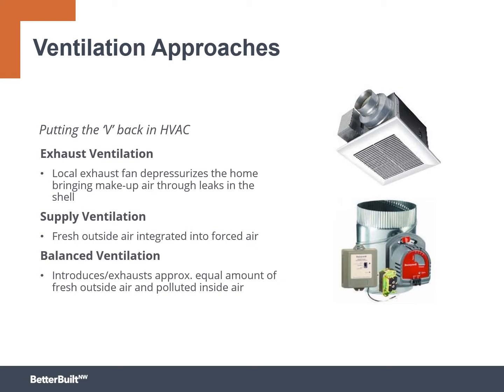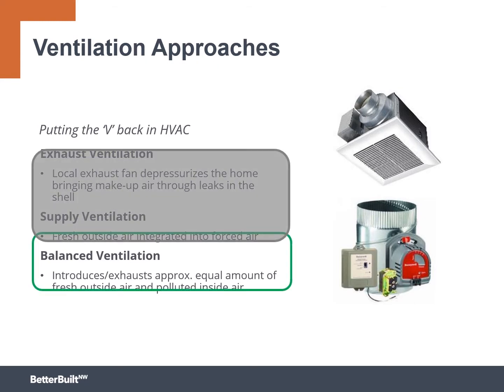There's a couple of different ways we can do it. We can think about exhaust ventilation. We can think about supply ventilation, and we can think about balanced ventilation. For today's session, we're really going to focus on the balanced ventilation, right? This is where we introduce and exhaust approximately an equal amount of fresh air and polluted air from the inside. The way this is typically described in code in the IRC and the IMC is that the exhaust and supply flows should be within 10% or 5 CFM of each other. So we're going to jump in now to really thinking through the balanced ventilation approach.